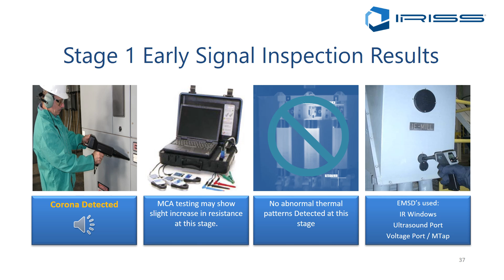As it gets worse, the motor current analysis, resistance and voltage testing start to show signs of failure. Thermal patterns begin to develop, showing signs of failure, and we may now move into hearing something called tracking, which sounds like this.